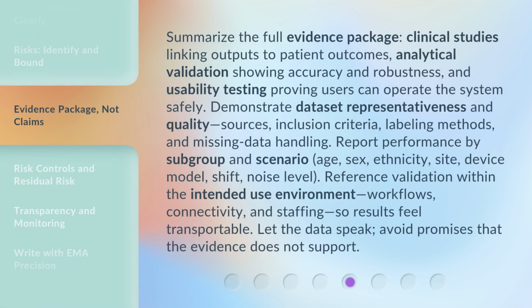Summarize the full evidence package: clinical studies linking outputs to patient outcomes, analytical validation showing accuracy and robustness, and usability testing proving users can operate the system safely. Demonstrate dataset representativeness and quality: sources, inclusion criteria, labeling methods, and missing data handling.